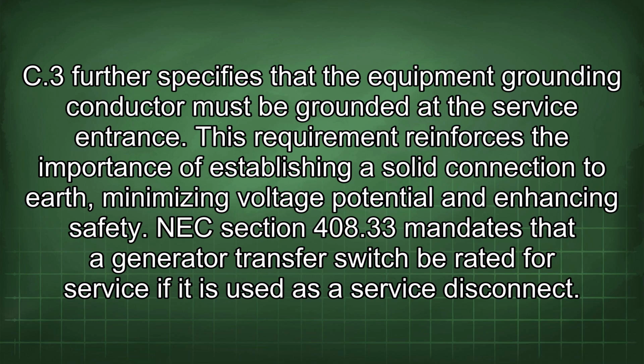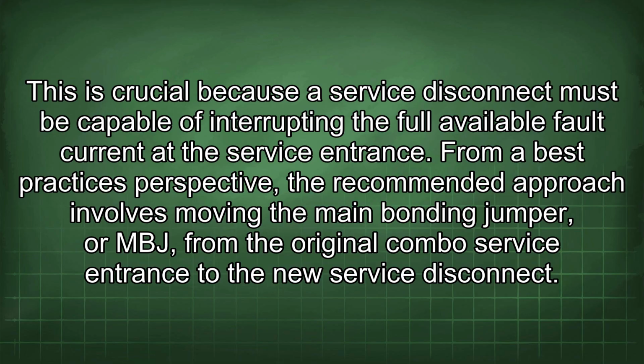NEC Section 408.33 mandates that a generator transfer switch be rated for service if it is used as a service disconnect. This is crucial because a service disconnect must be capable of interrupting the full available fault current at the service entrance.